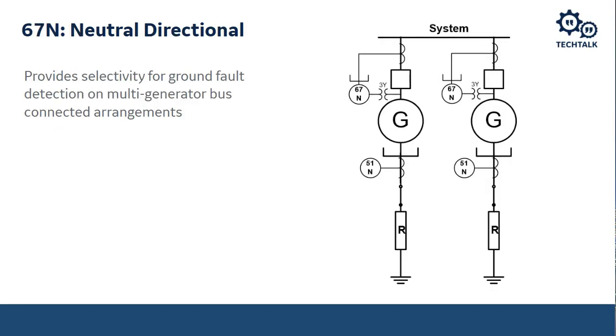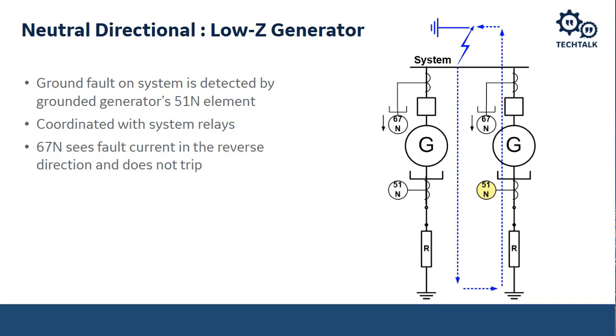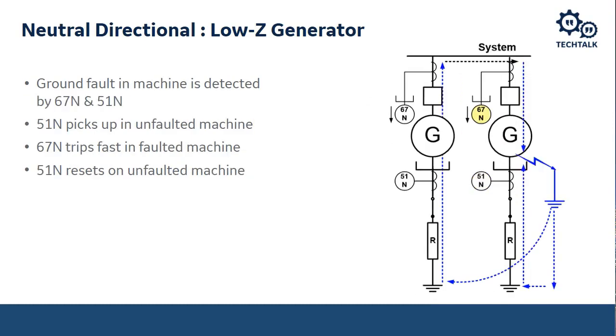With the 67, especially when you have a bus connected generator, or as we mentioned, generators connected to the same bus, it's going to be difficult to locate the fault with just the 51 element. If the fault is on the adjacent generator, both of these 51N neutral overcurrent elements will pick up and trip for that fault because they're seeing the same fault currents. Whereas the 67N only looks into the generator.